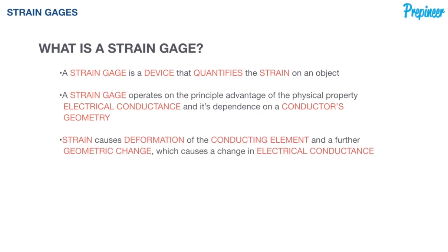A single strain gauge or multiple for that matter can be attached directly to any object or system of elements using some special form of adhesive. After being put into this position, the strain gauge and more specifically the conductor within that strain gauge experiences deformation at the same rate of the object which it is placed on. This deformation causes the conducting element to deform and due to this change in geometry, causes a change in electrical resistance that can be measured and attributed to the associated strain.